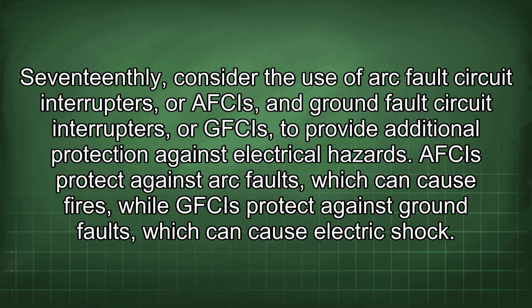17thly, consider the use of arc fault circuit interrupters, or AFCIs, and ground fault circuit interrupters, or GFCIs, to provide additional protection against electrical hazards. AFCIs protect against arc faults, which can cause fires, while GFCIs protect against ground faults, which can cause electric shock.